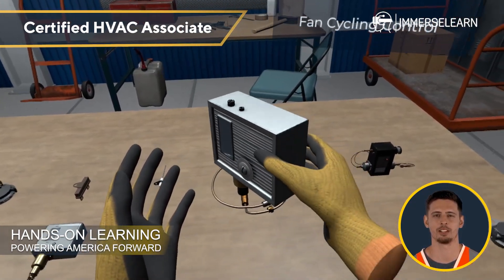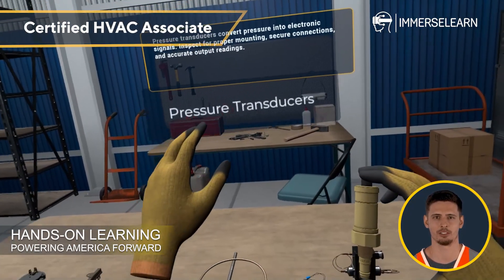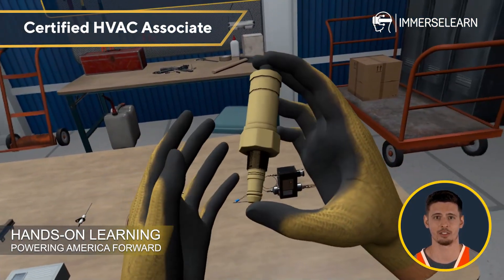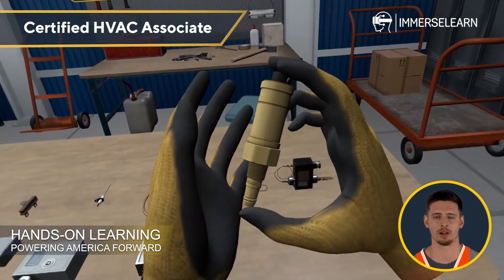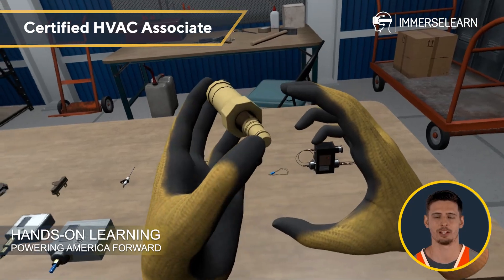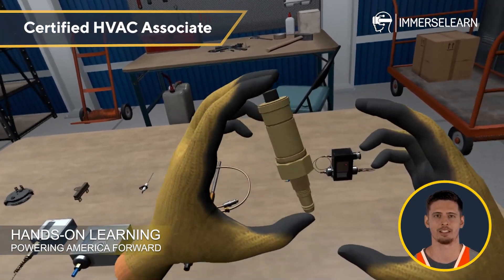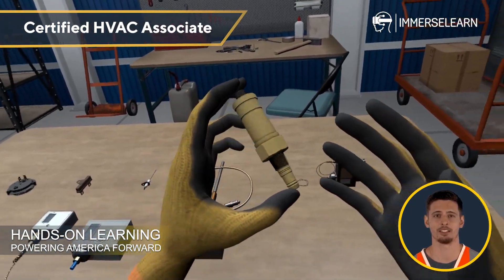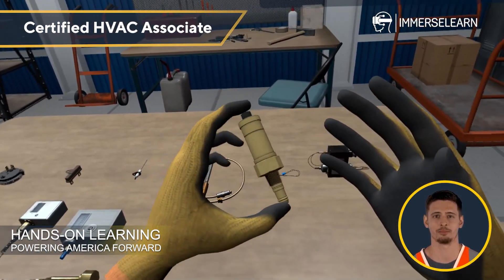Similarly, pressure transducers convert pressure into electronic signals. Checking for proper mounting, secure connections and accurate readings is key to maintaining system efficiency.